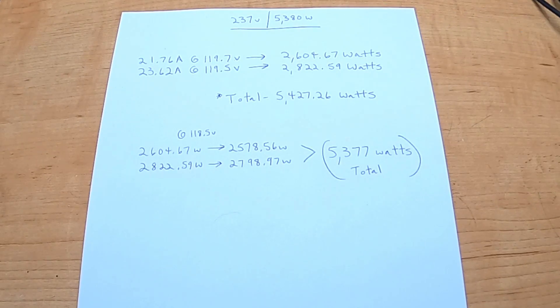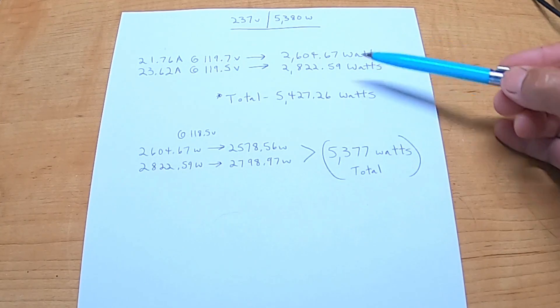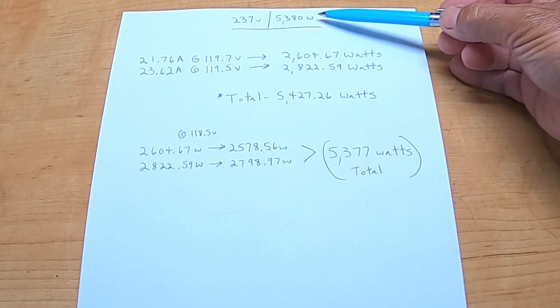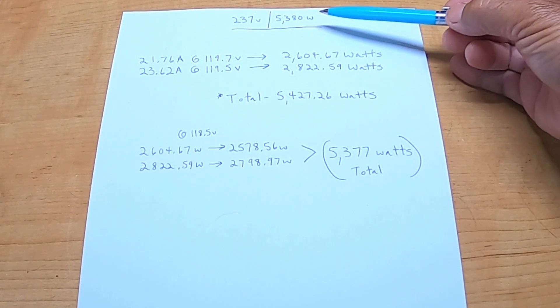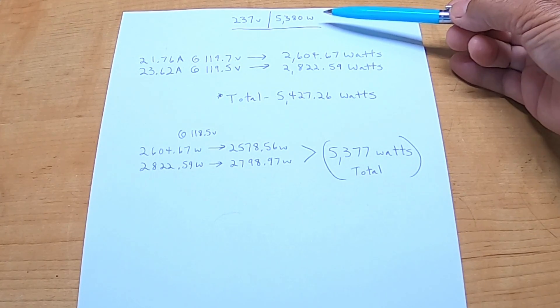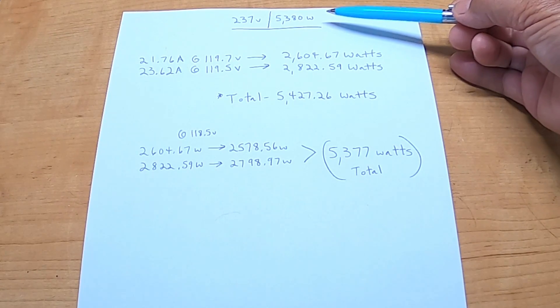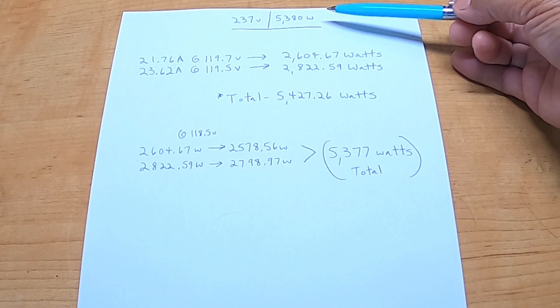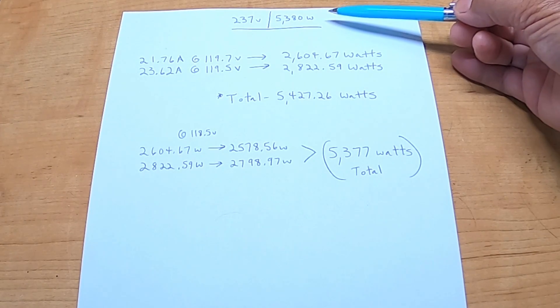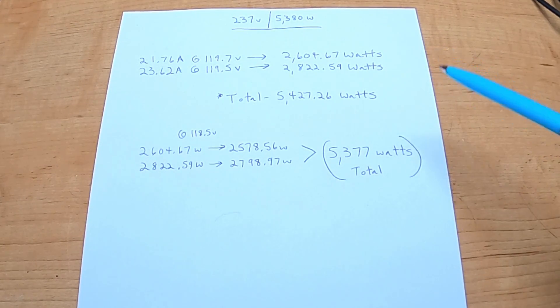There is nothing wrong with that meter. If you do this calculation and your amount is way below what's shown on the meter, you'll need to call the power company and file a complaint that the meter is not properly calibrated. They'll send someone out to inspect and either calibrate or swap out the meter. If your number is higher, you're actually beating the power company — you're using more power than they're charging you for. Just be careful when reaching inside the electrical panel to take measurements.